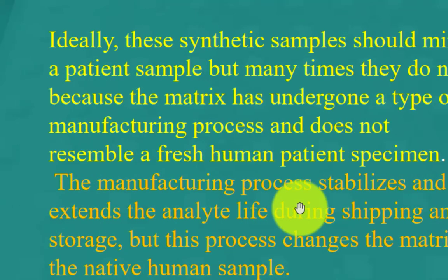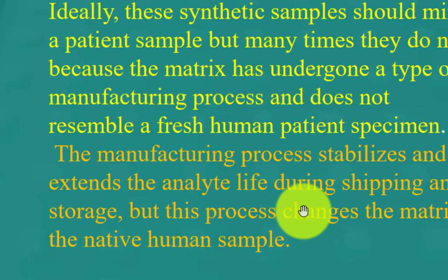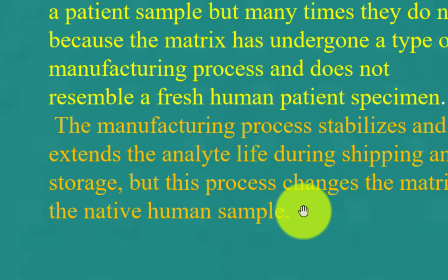Ideally, these synthetic samples should mimic patient samples, but many times they don't because the matrix has undergone a type of manufacturing process and doesn't resemble a fresh human patient specimen.